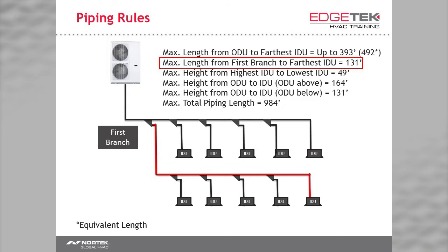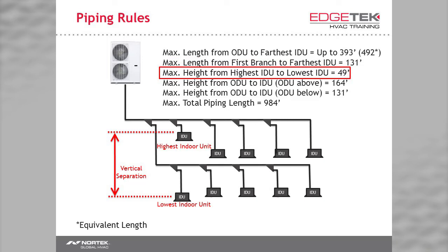So if we were to follow the piping from the outdoor unit, we'll eventually reach a Y branch. This is known as the first branch. There is only one first branch no matter how you try to pipe the system. So the distance from the first branch to the farthest indoor unit must be less than 131 feet. This is important. If you are more than 131 feet, you need to move your first branch or last indoor unit.